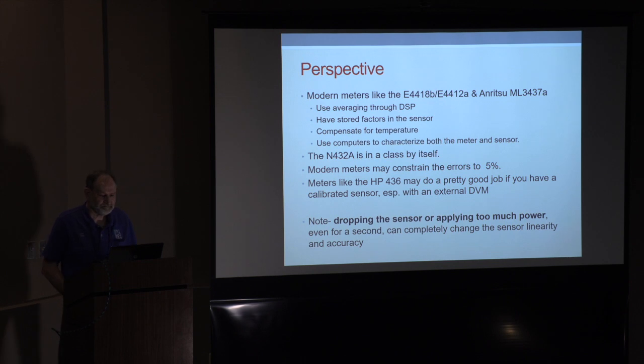So modern meters like the HP or Keysight 4418 and the Anritsu 3437, they try to do a lot of work on taking out some of the biggest errors like having an EEPROM that stores the correction factors. So when you plug it into the meter, it automatically sets all that up, and you just tell it you're working at 10 gigahertz, and you're not making a mistake, because I'm sure that they found that on a practical level, technician level, that people were making a mistake with the compensation settings and getting wrong readings. So that helps.